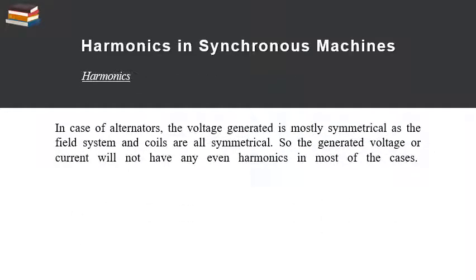In case of alternators, the voltage generated is mostly symmetrical as the field system and the coils are all symmetrical. So the generated voltage or current will not have any even harmonics in most of the cases.